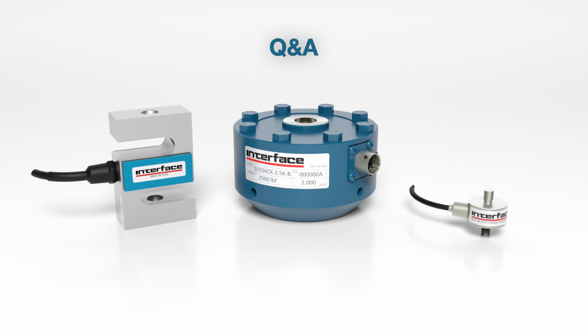Okay, this is going back to that 100K shunt. We are performing our own calibrations on site using the 100K shunt. Will linearity and hysteresis be affected by selecting points other than 5 up, 1 down? We do 5 up to full capacity, then back down to 0. Is this acceptable?